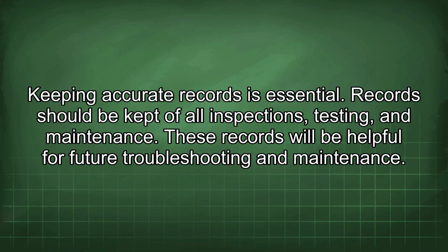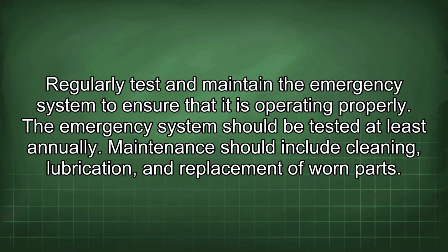Keeping accurate records is essential. Records should be kept of all inspections, testing, and maintenance. These records will be helpful for future troubleshooting and maintenance. Regularly test and maintain the emergency system to ensure that it is operating properly. The emergency system should be tested at least annually. Maintenance should include cleaning, lubrication, and replacement of worn parts.